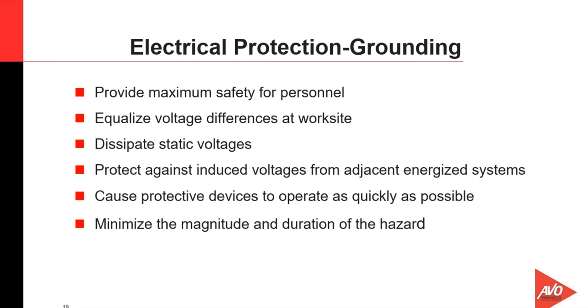Other types of issues that are there, like static voltages, induced voltages, capacitive coupled voltages, those types of voltage sources are also diminished or rerouted so that the issues don't create a problem for the worker. The other issue with PPE grounds is to provide a real low impedance path to ground so that we can operate the upstream protective devices as quickly as possible and overall minimize the magnitude and duration of the hazard by quickly de-energizing the system. Remember, when grounds have to operate on an accidental activation, something has already gone wrong with our energy control program because we're energizing a feeder with PPE grounds on it. So they have to do the job. In order to do the job, they have to be sized properly and rated properly and installed properly.